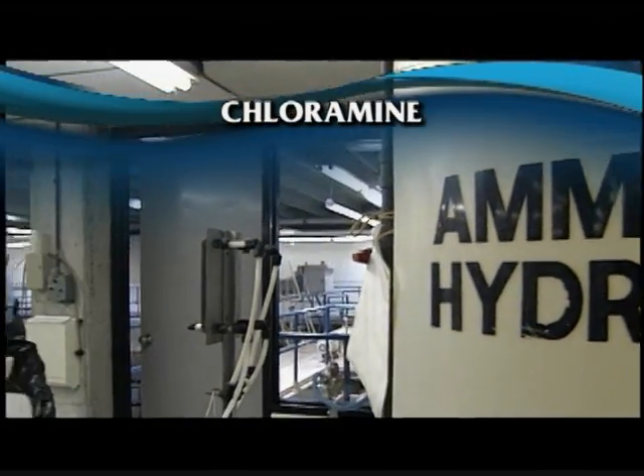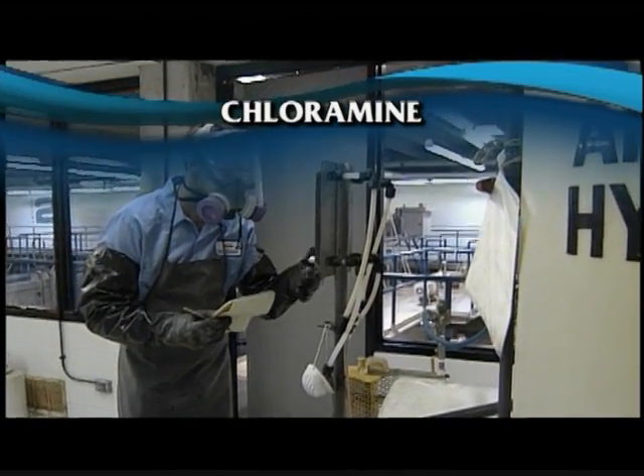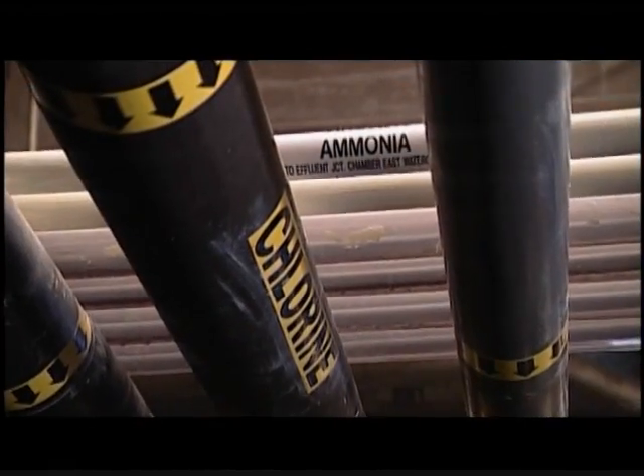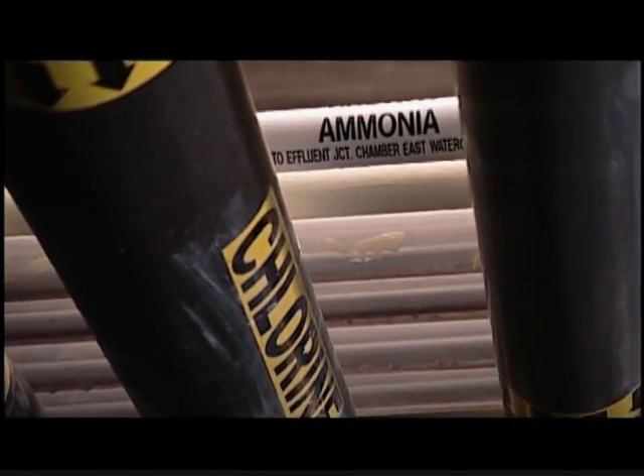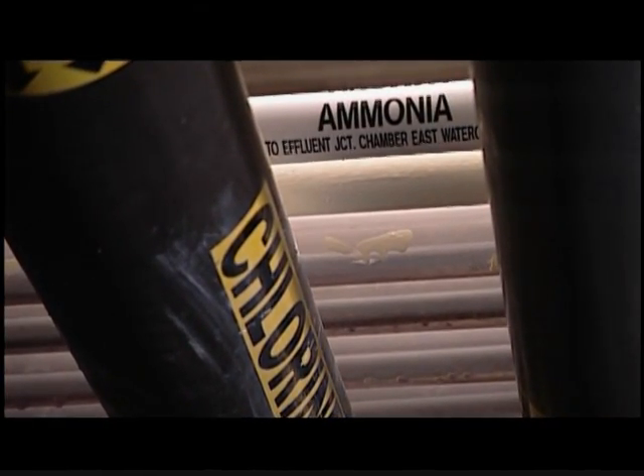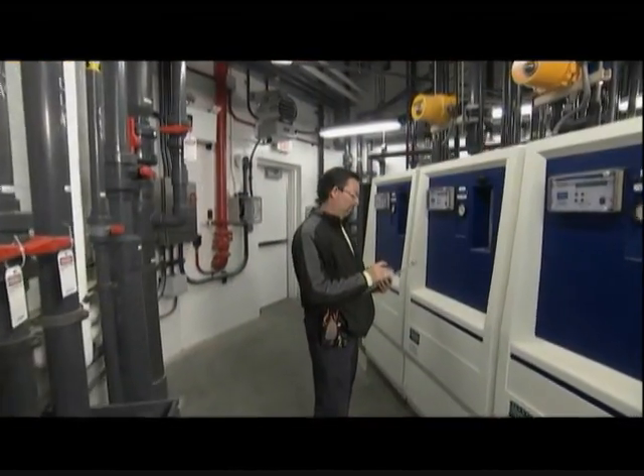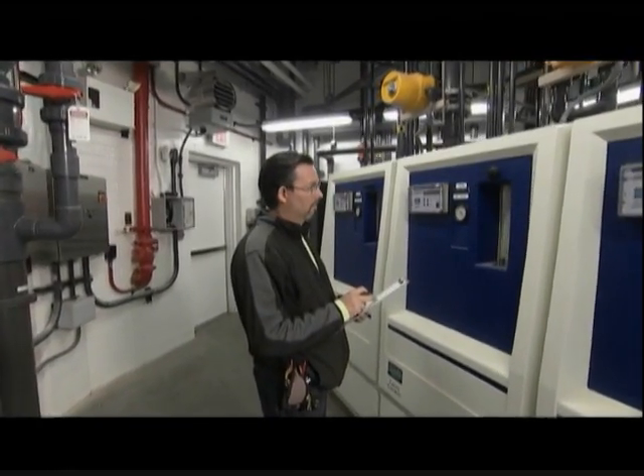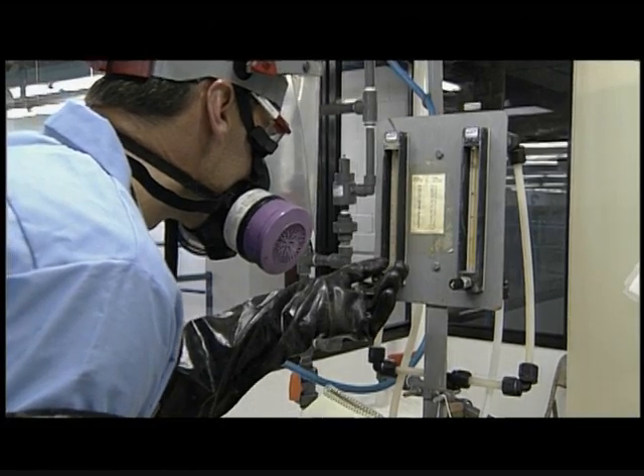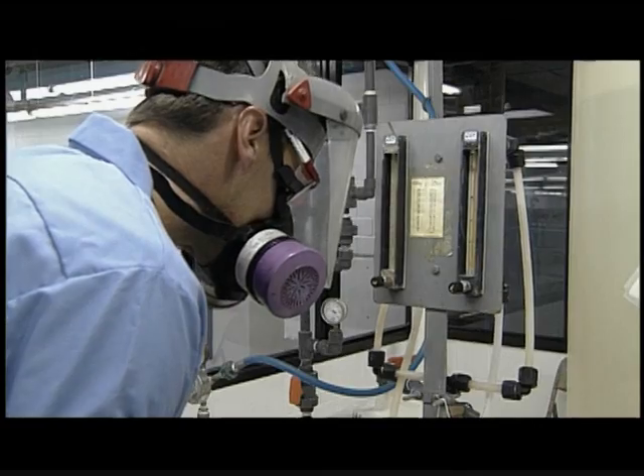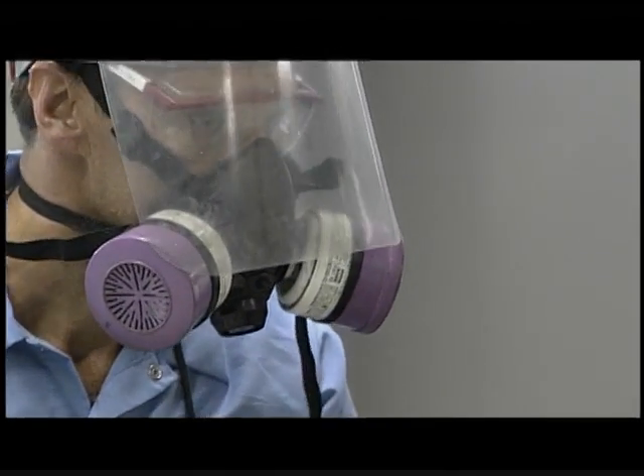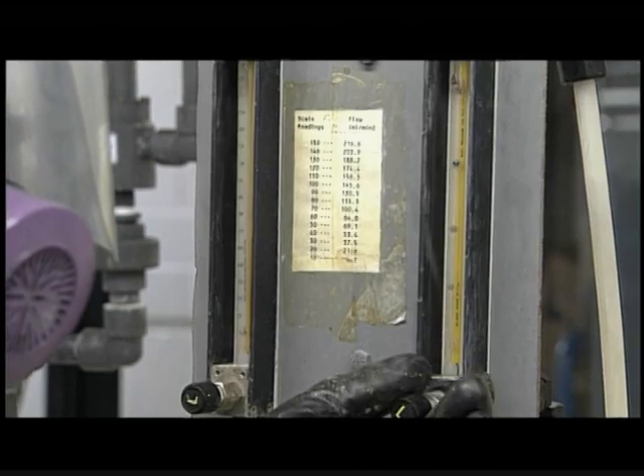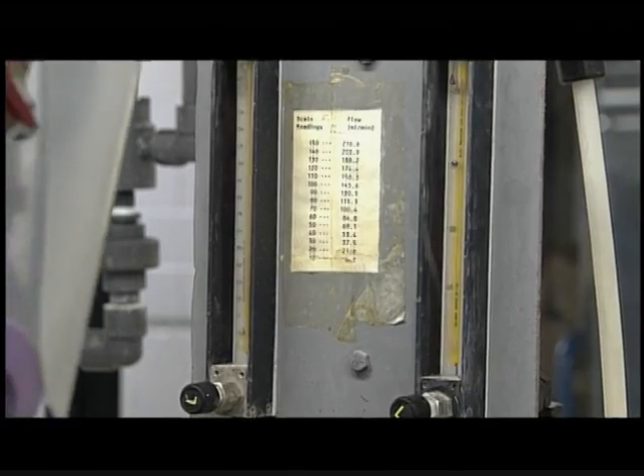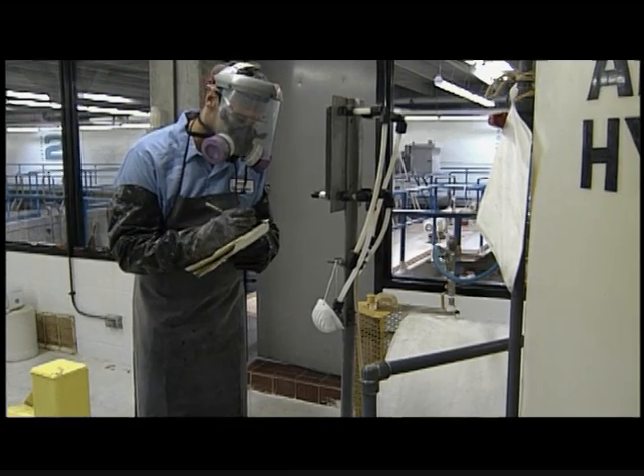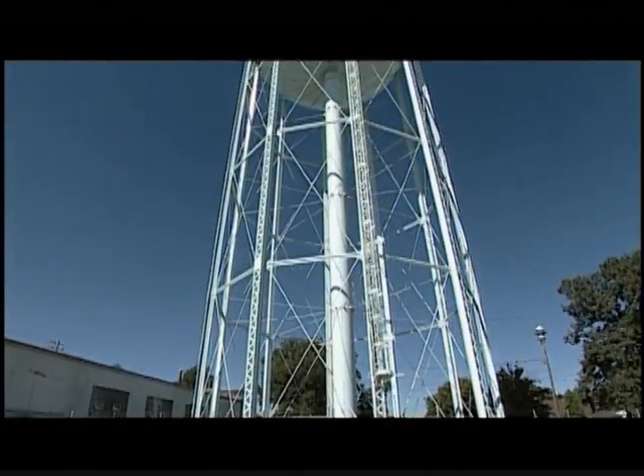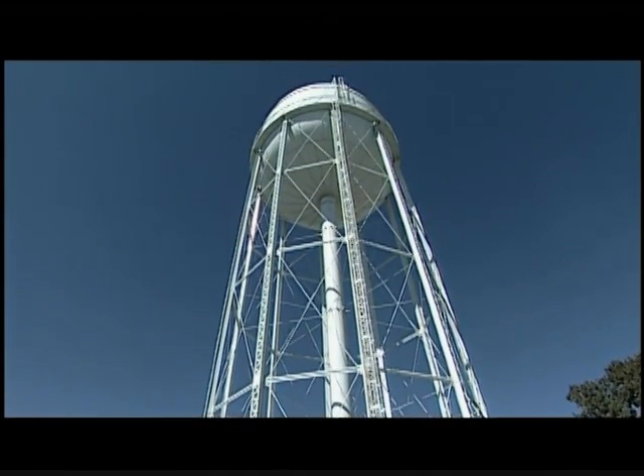Next is chloramine, also called combined chlorine. Chloramine is typically created by addition of ammonia to free chlorine already present in water. Like chlorine, chloramine has a proven track record. Operators add ammonia and chlorine to form monochloramine, or simply termed chloramine. While not a highly effective primary disinfectant, chloramine is an effective secondary disinfectant for maintenance of a residual in the distribution system.